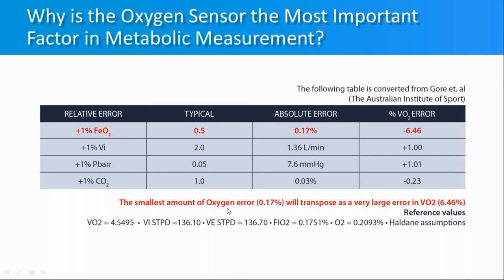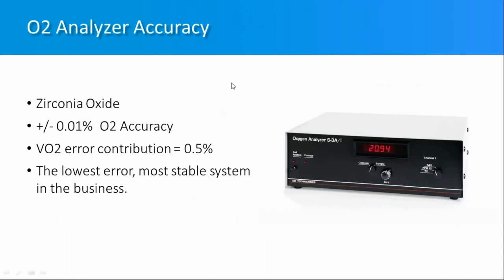The MOXUS system uses a zirconia oxide cell for oxygen measurement, which is not typical in many metabolic systems but is the basis for the system's success. The zirconia oxide cell runs at about 700 degrees inside the cell. Its accuracy is very high and its VO2 contribution is very low compared to most other systems. Zirconia is also extremely stable over a long period of time.